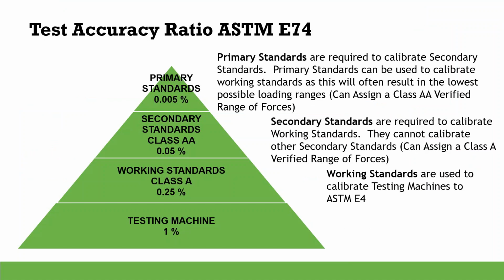So we talk about a pyramid. Here's another pyramid. ASTM is built on test accuracy ratios, which a lot of people may say boo, boo, boo. However, when it is confined to a standard and people follow that standard, it can work really well. So what happens with E74 is they say primary standards are required to calibrate secondary standards. Primary standards can be used to calibrate working standards, as this will often result in the lowest possible loading ranges. You can use primary standards to calibrate anything below this on the pyramid. It's kind of hard with the testing machine, but it's still doable if you hang weights. Secondary standards are required to calibrate working standards. They cannot calibrate other secondary standards.